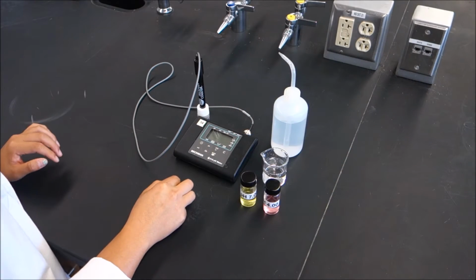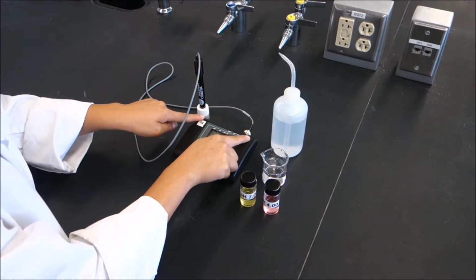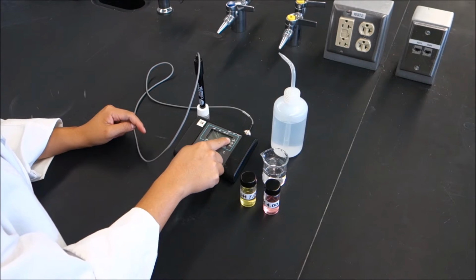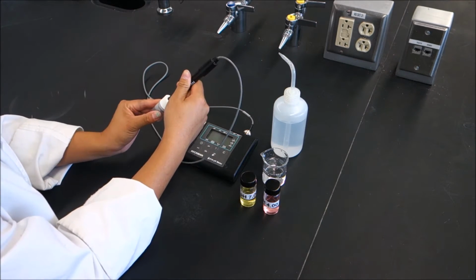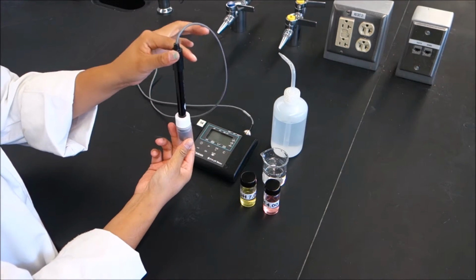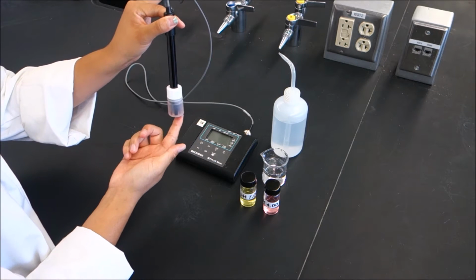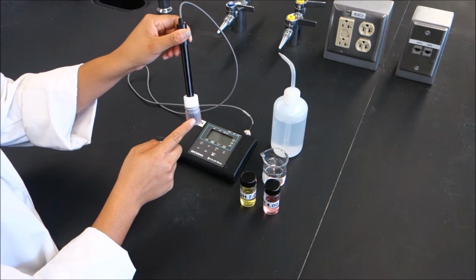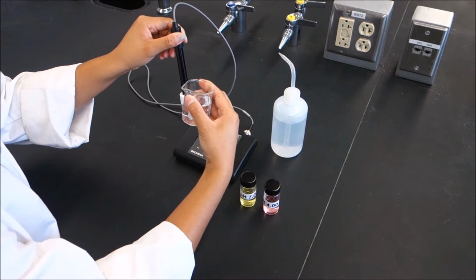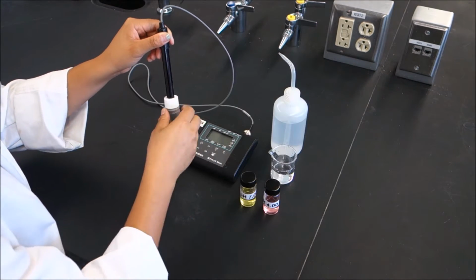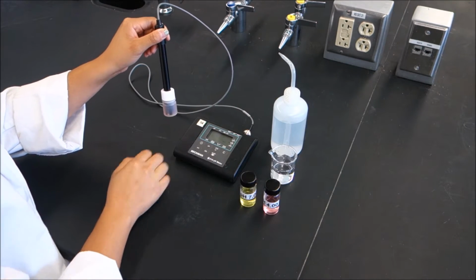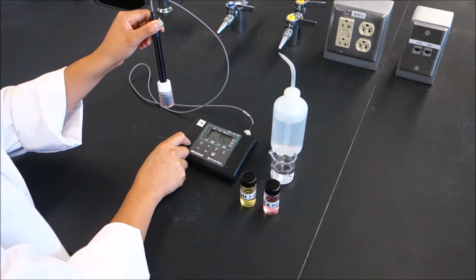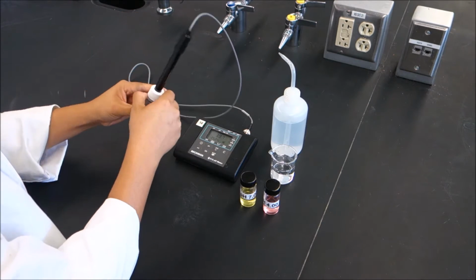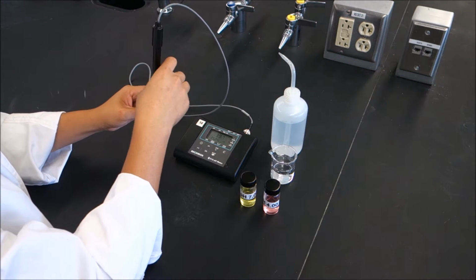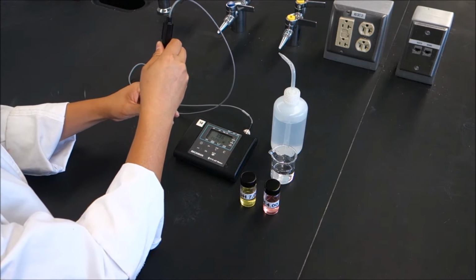A few things we want to mention about this meter. This here will give you the readout of the pH, and this here is your probe. You always want to keep this probe upright and in some kind of solution, whether it be the buffer solution or just a beaker of DI water. So let's go ahead and turn on the pH meter. What we have to do first is calibrate the meter before we use it to read anything.